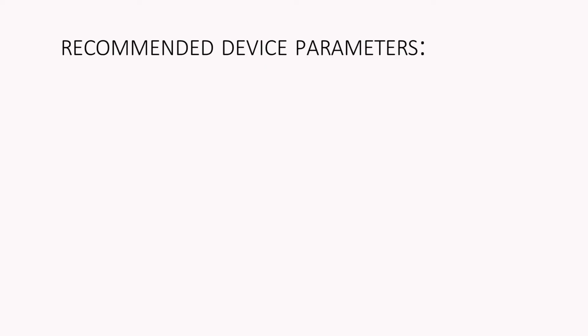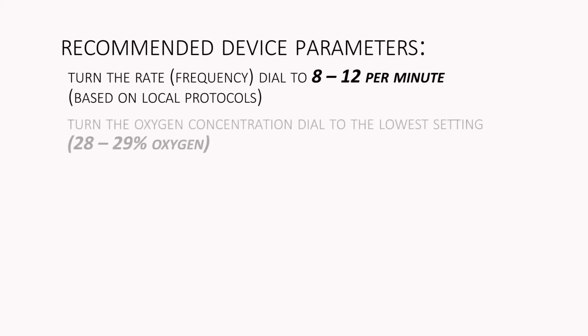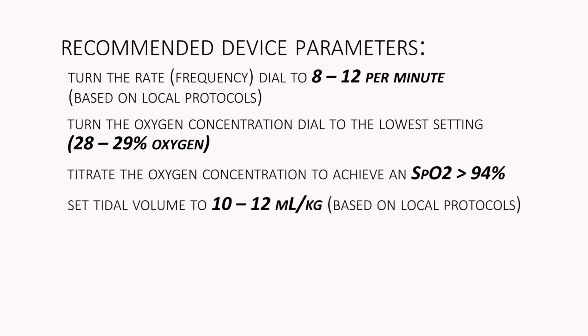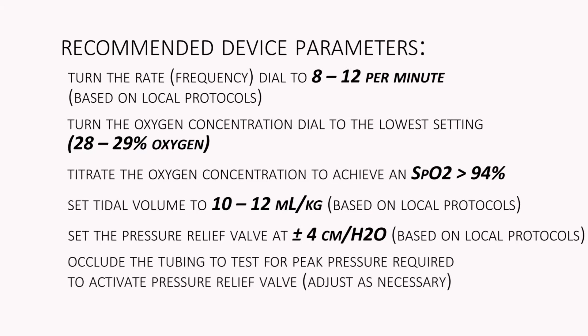Recommended device parameters are: turn the rate dial to 8 to 12 per minute, turn the oxygen concentration dial to the lowest setting between 28 and 29 percent oxygen, and titrate oxygen concentration to achieve an SpO2 greater than 94 percent. Set tidal volume to 10 to 12 milliliters per kilogram. Set the pressure relief valve at plus or minus 4 centimeters of H2O. Occlude tubing to test for peak pressure required to activate the pressure relief valve and adjust as necessary.